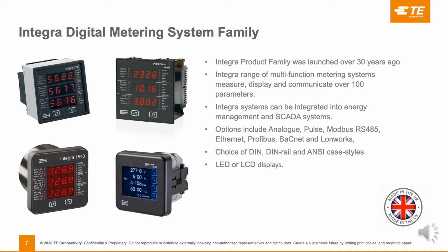The Integra range is a range of multifunction power meters to measure, display and communicate over 100 parameters. The power quality meter, which is our 2270, is a true power quality meter and displays way over the 100 parameters. These products can be in the choice of LED or LCD displays and have a choice of DIN, DIN rail and ANSI style cases. A lot of the difference between the meters is based on the outputs as well, where we have analog outputs. Pulse and Modbus is more standard, but we also offer Ethernet, Profibus, BACnet and LonWorks communications.